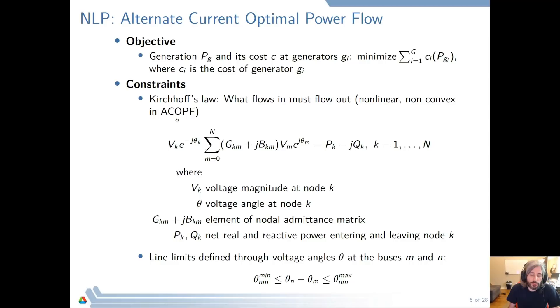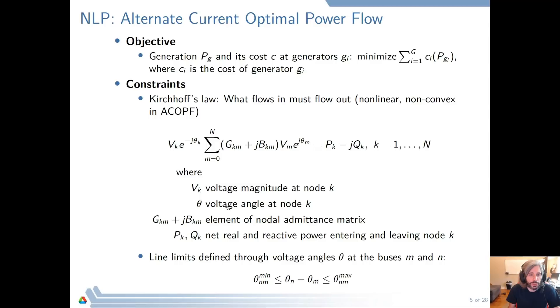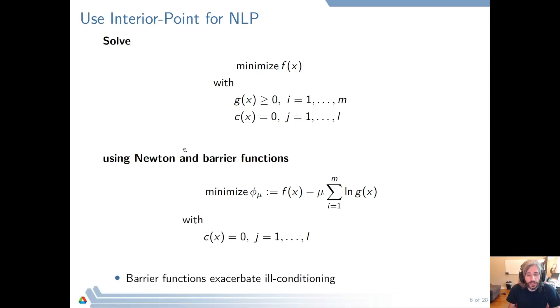What we actually solve per power flow case is the optimal power flow — the most cost efficient way of generating power. The power generation goes into the cost function and has some parameters associated with each generator. Then we have the Kirchhoff laws of a flow problem: what flows in must flow out. We also have line limits, and these tend to be the hard part — they are inequalities, whereas the Kirchhoff laws are equalities.